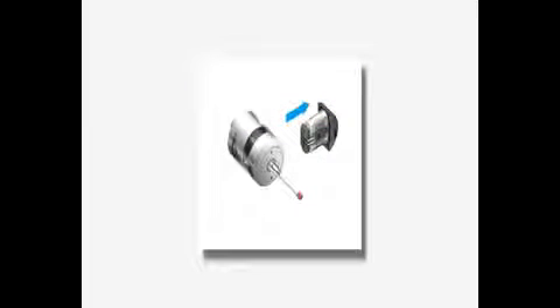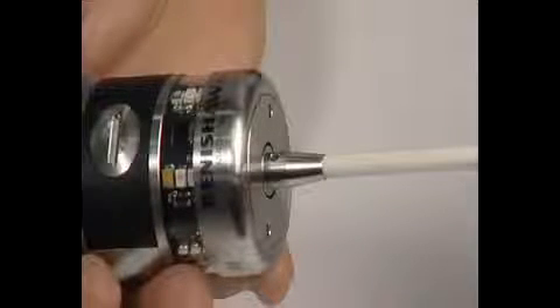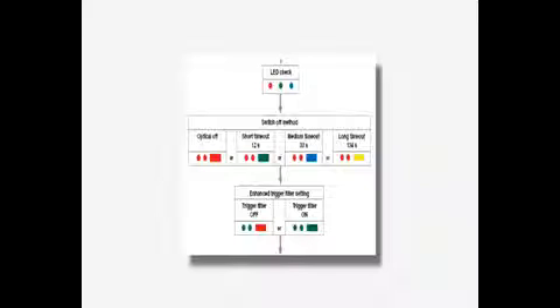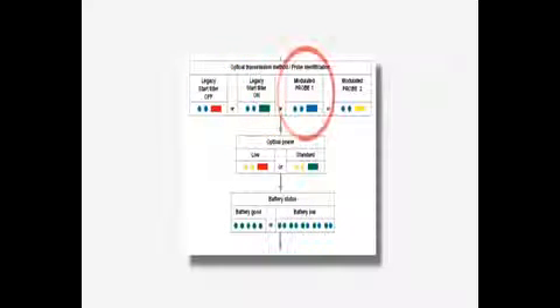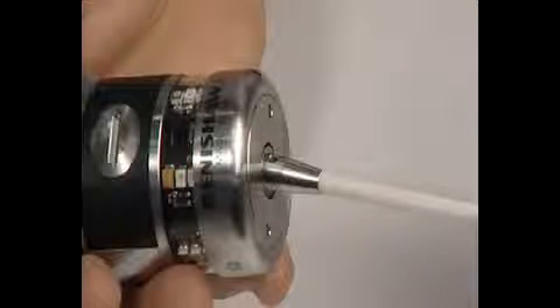To enter the OMP40-2 Trigger Logic Settings menu, remove the battery cassette for 5 seconds, deflect the stylus, and, keeping the stylus deflected, replace the battery cassette. Once the battery cassette is installed, keep the stylus deflected for a further 15 seconds, then release it. Once the review sequence is complete, the user has the option to change each mode by deflecting the stylus for about 1 second. To move to the next option, the stylus should be deflected for at least 4 seconds.